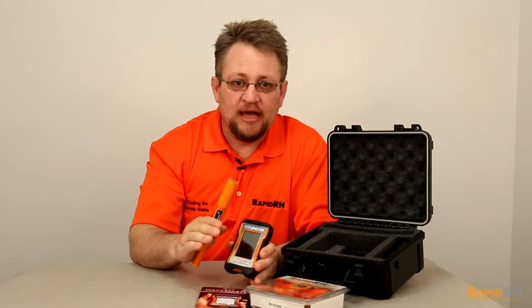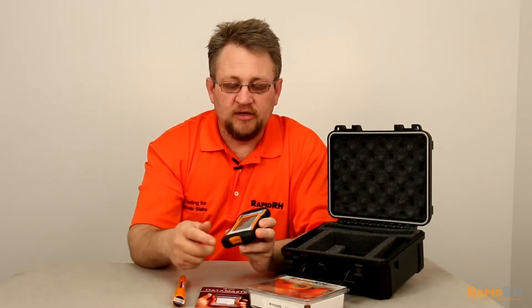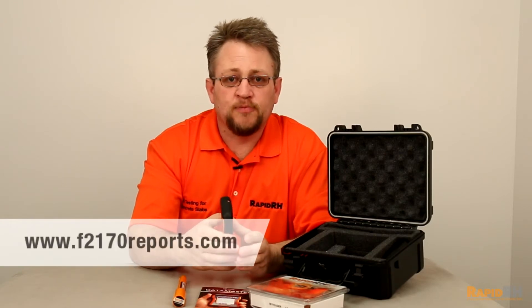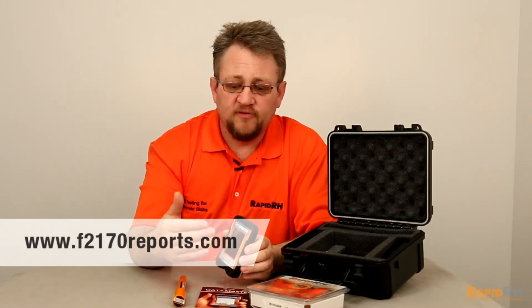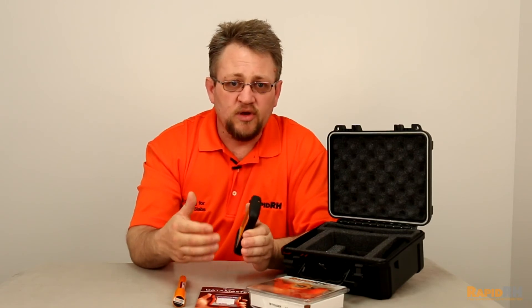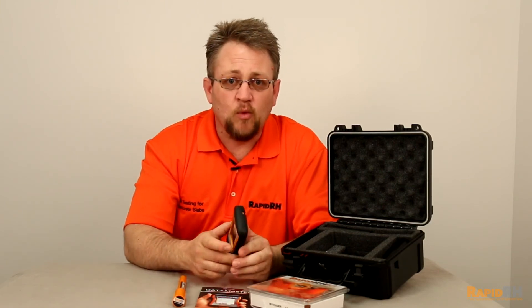Once you've completed the job and want to send the information off to your client, all you have to do is plug it in via USB or via an SD card and upload it to a website we've designed just for this product called f2170reports.com. It will upload all the information, look at all the serial numbers from the sensors you've taken out of the concrete, compare them against our manufacturing log, and ensure that all of those sensors are within their window of calibration. Once that's done, it actually prints on the bottom that the report is certified by Wagner Meters. This is Jason Spangler signing off.